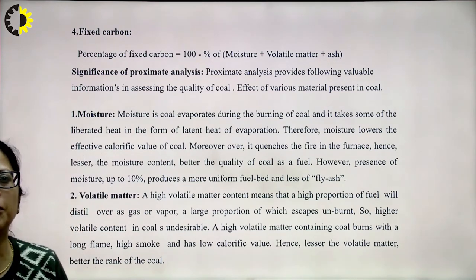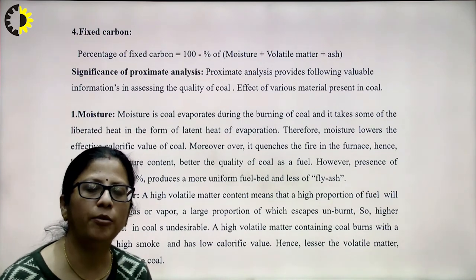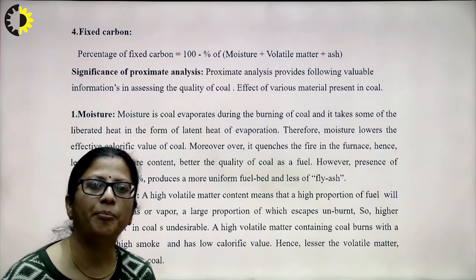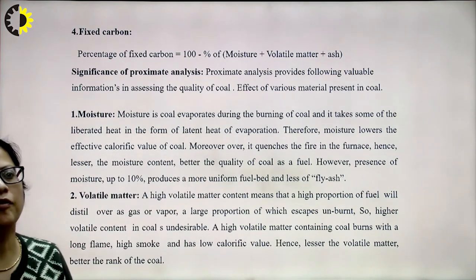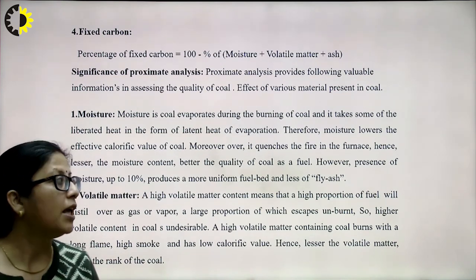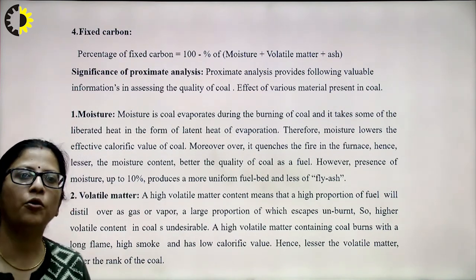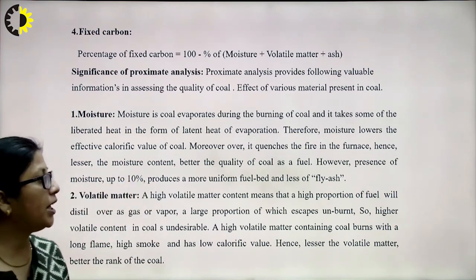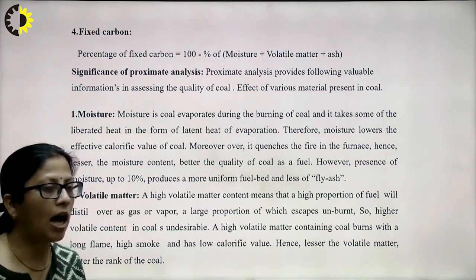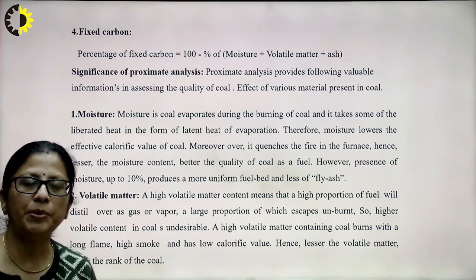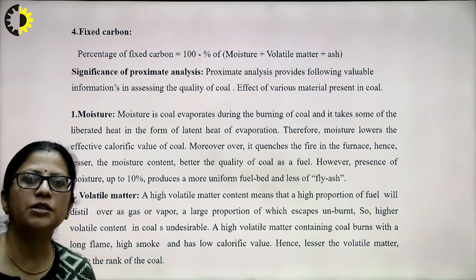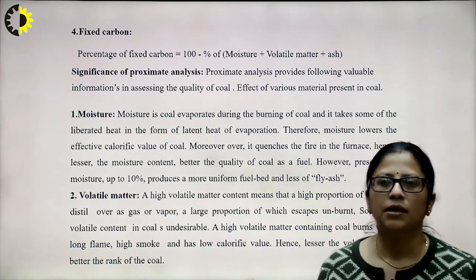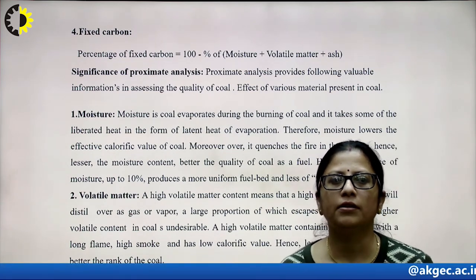The significance of proximate analysis is that it provides valuable information for assessing the quality of coal. Regarding moisture: it evaporates during burning and absorbs liberated heat as latent heat of evaporation, thereby lowering the effective calorific value. It also quenches the fire in the furnace. Therefore, lesser moisture content means better quality coal, though up to 10% moisture produces a more uniform fuel bed and less fly ash.